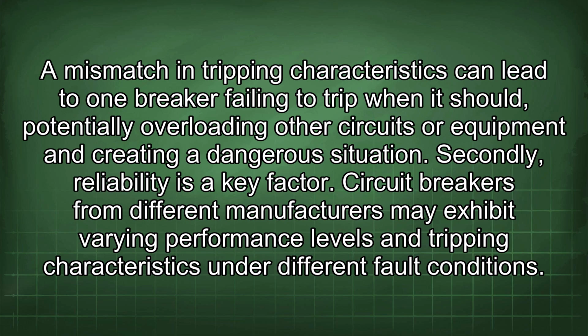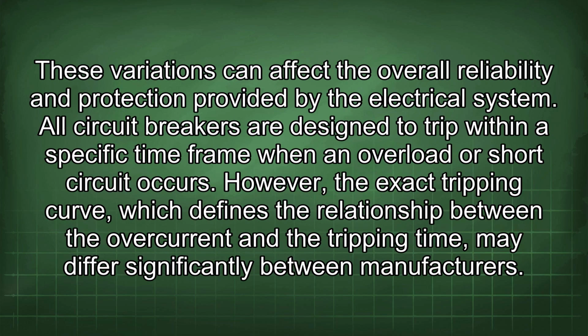Secondly, reliability is a key factor. Circuit breakers from different manufacturers may exhibit varying performance levels and tripping characteristics under different fault conditions. These variations can affect the overall reliability and protection provided by the electrical system.